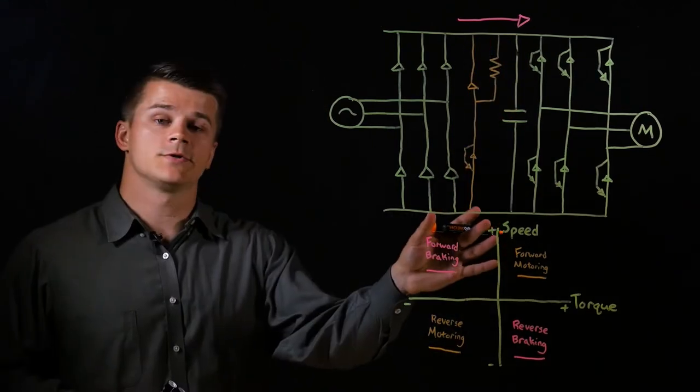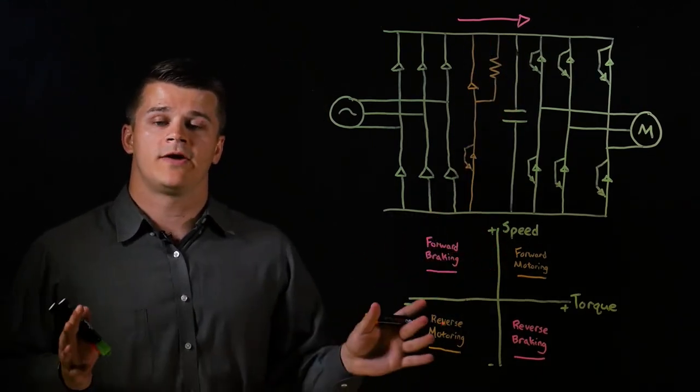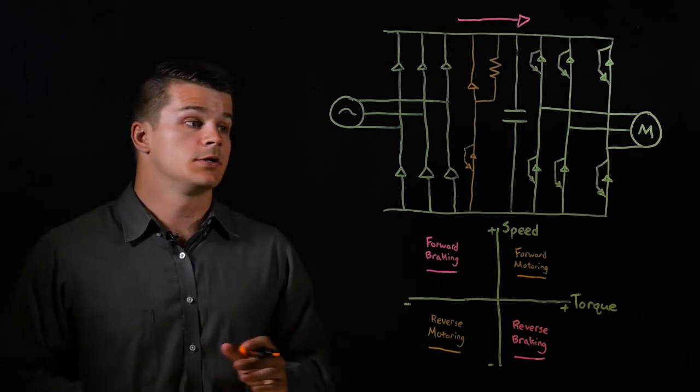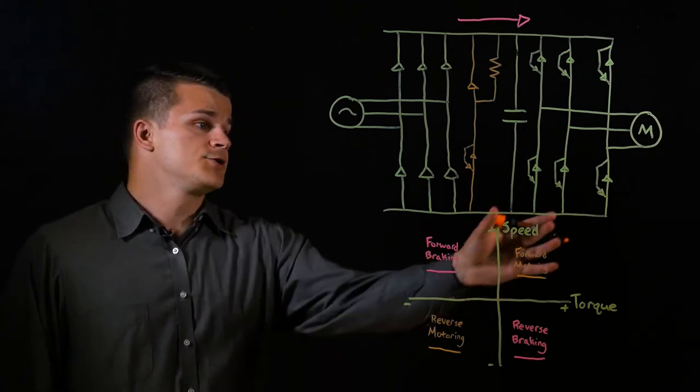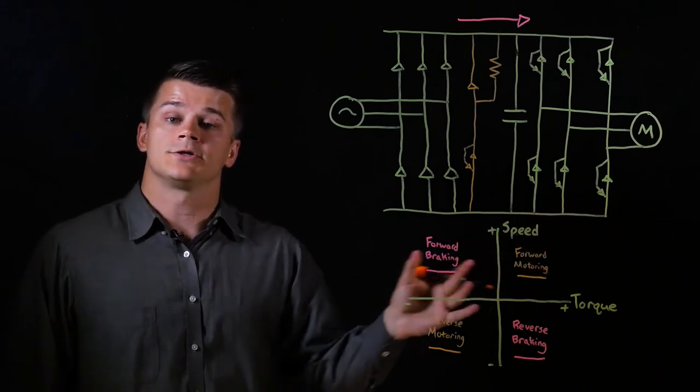What I've just added is a braking resistor circuit to the VFD. Whenever the motor is in a generating operation, the drive must dissipate the excess energy generated; otherwise, you risk damaging the IGBTs and causing a drive failure.